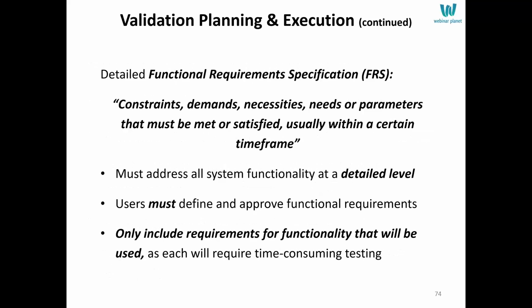Based on the URS, you're going to break that down into very detailed, granular functional requirements. Every function at a detailed level. And users should define and approve these. But again, they don't have to approve them all before you start work, before your vendor starts work.